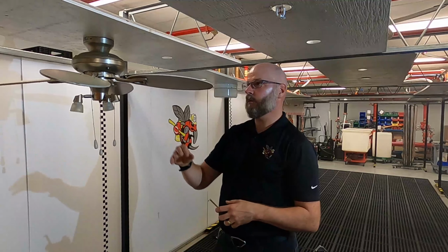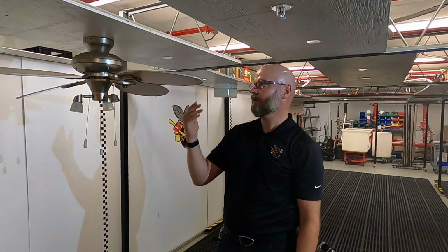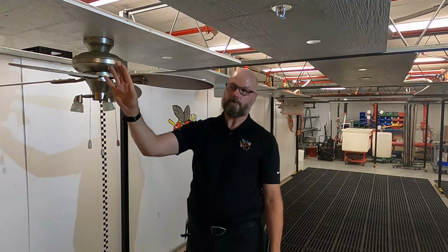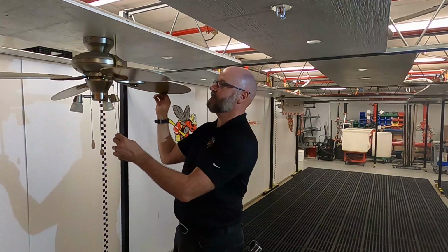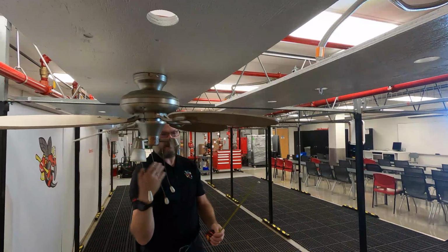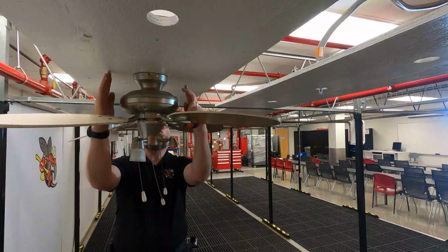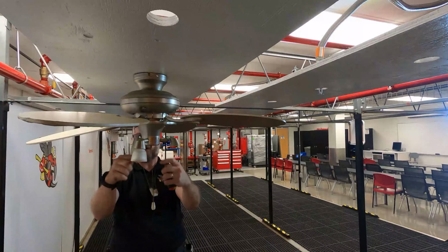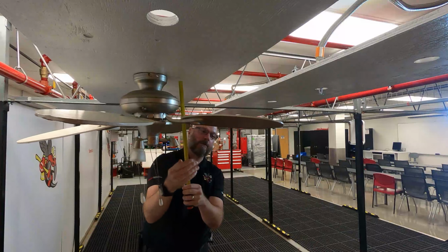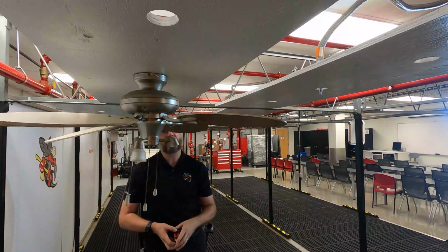So in the event that we're fortunate enough to deal with smaller fan blades, again we go back to that thought of, well, what's the first thing water's really going to hit? It's going to be the outside motor housing. So for that, we just measure the distance down for the motor housing. And with all of these different parts of the light to be thoughtful of, again, I tend to be more conservative. I try to think of this as drawing a straight box straight down and straight across. That's a very conservative approach, but there's no allowances within our obstruction tables for something of an unusual shape like the ceiling fan.